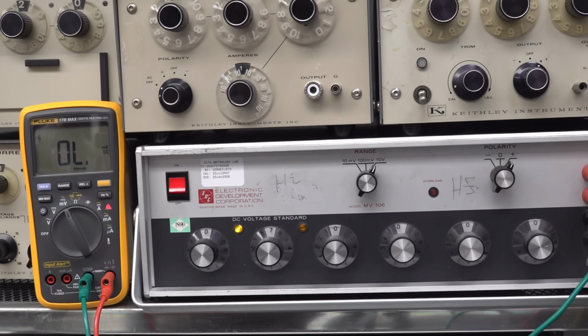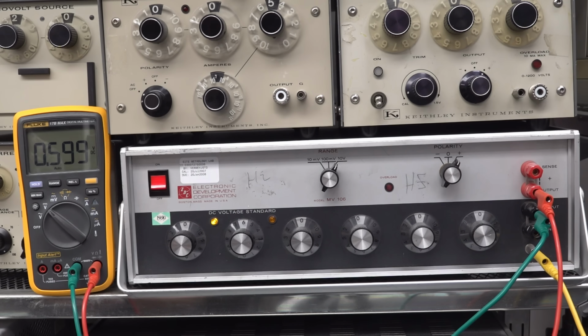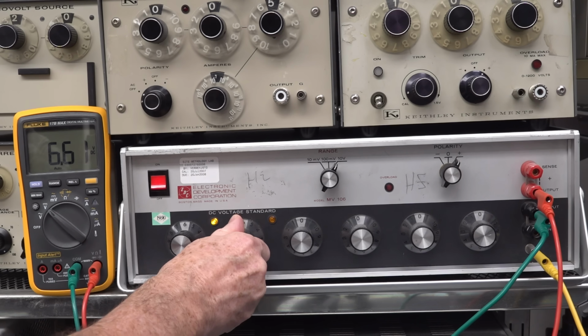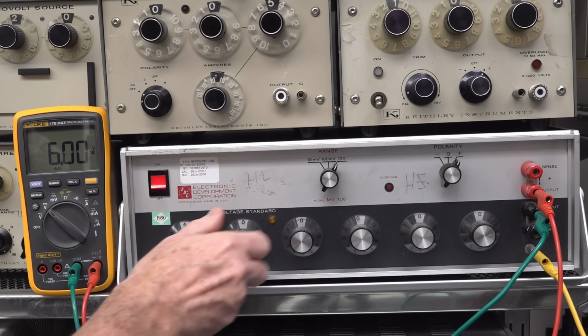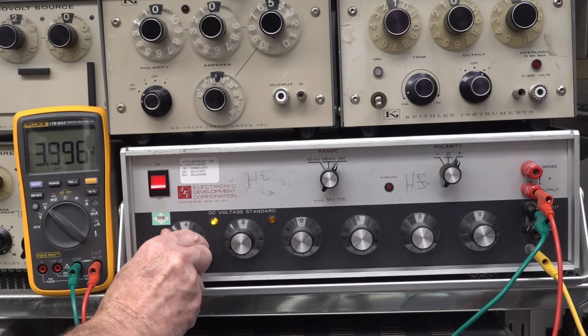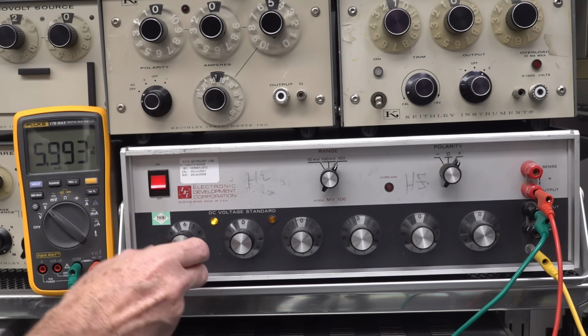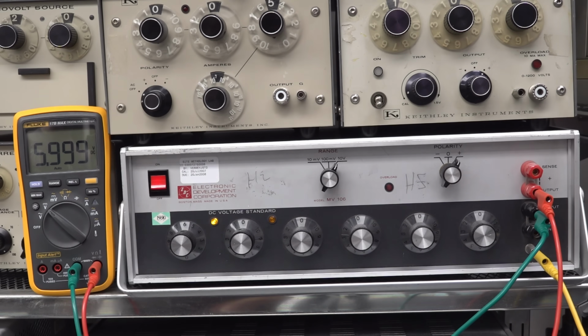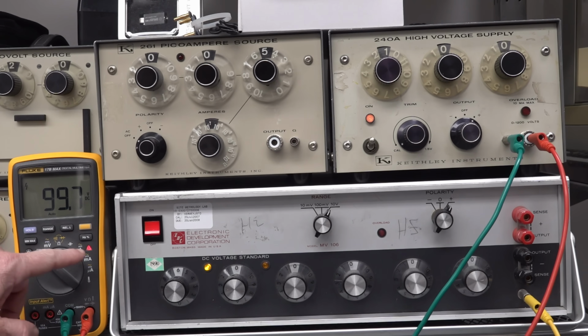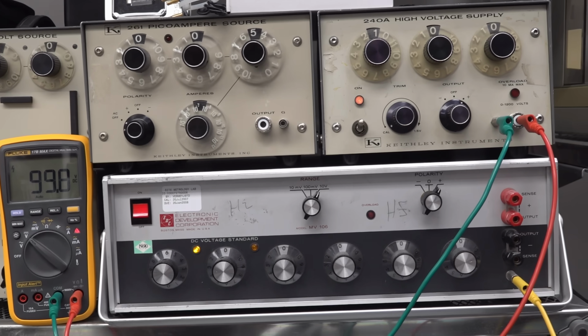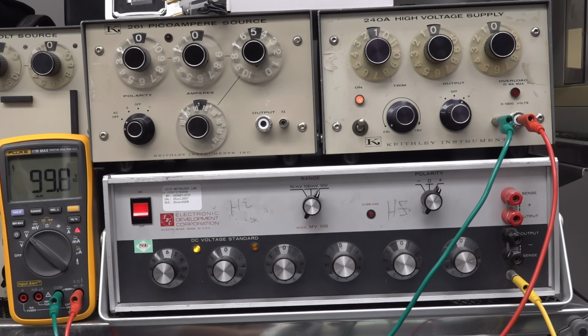Oh my goodness. Why? If I go up a range, there you go. It is one digit out, 6.6. Let's go back. I'm going to have to drop it down because it's going to range. And 6 volts. Oh, there you go. Yep, it got there. And sure enough, at 100 volts, our high voltage indicator comes on. So I'm going to deem that to be a bug. That's got to be a bug, right? Unless you've got some other reason why it would do that in the millivolt range. Unbelievable.